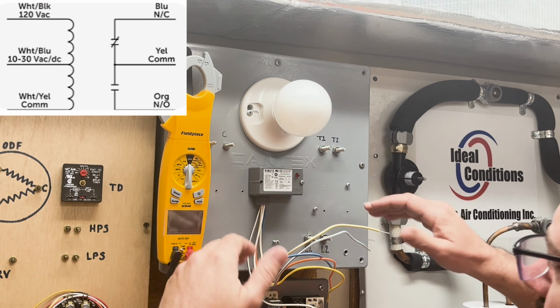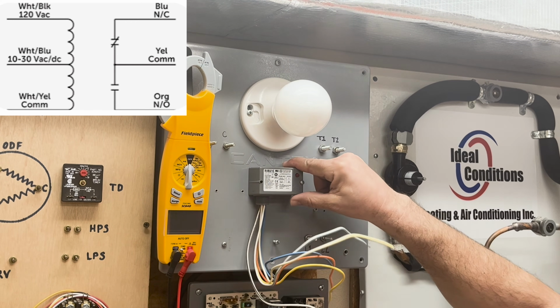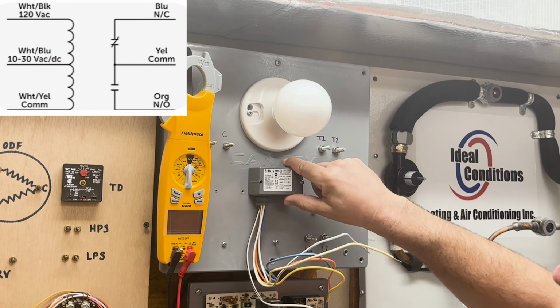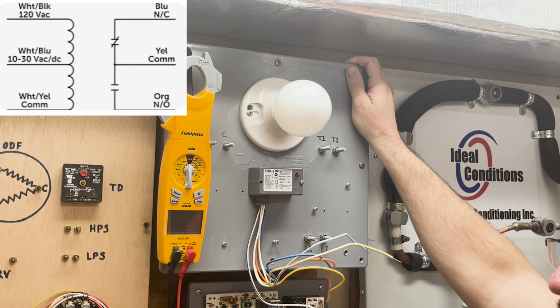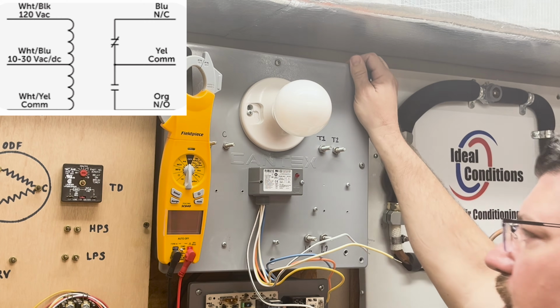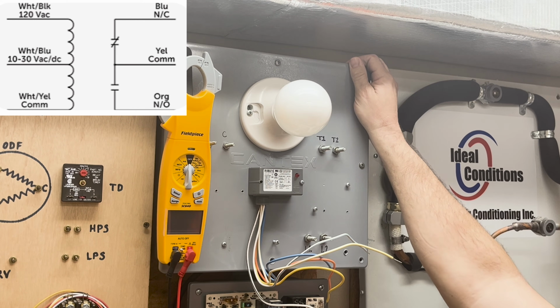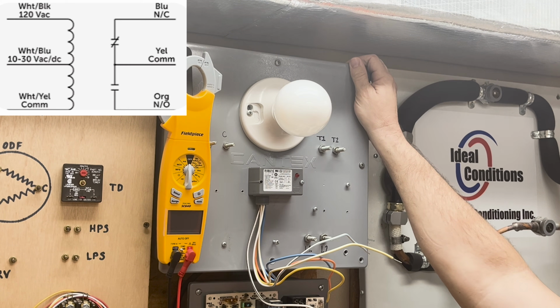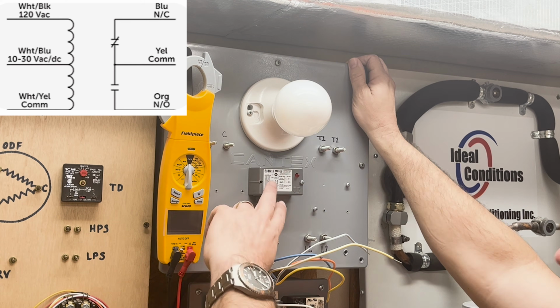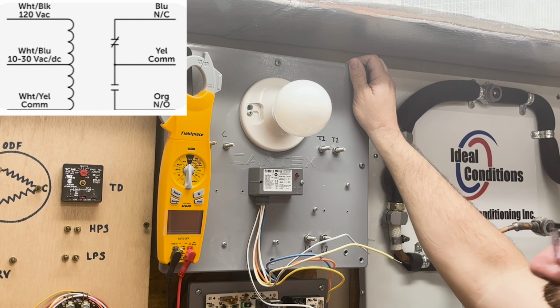All right, the CANTEX box, we're going to talk about the RIB relay. A lot of people don't understand what the RIB relay is for. Typically, if you do industrial work or any type of building automation, you're going to run into a lot of 120 applications, DC applications, and VAC applications on the low voltage 24 volt side. And so this relay is typically stocked because anything that needs to happen, there are just more applications that you can use that particular relay for. And so you can use this relay in a residential application. We're going to talk about how to do that today.